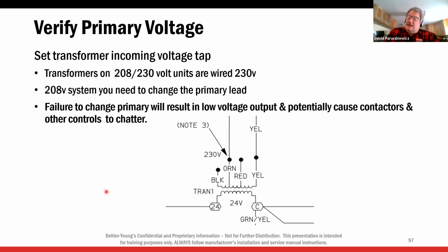So, transformer primary. I can't tell you how many times on job sites we go out and we find this, and something so simple can cause all kinds of problems. We have 208, we have 230. I think guys are used to motors being multi-voltage. Transformers are too, but you have to wire them accordingly. If you have 208, meaning you check the primary voltage, it's 208 volts, I have to set the taps on the transformer for 208. If I have 208 and I have the transformer set up for 230, I'm going to have low secondary voltage. I might have 22 volts. And it might work sometimes. Your contactors might chatter. You might burn contactors up. So this seems like a really simple thing, but it gets mixed up all the time.